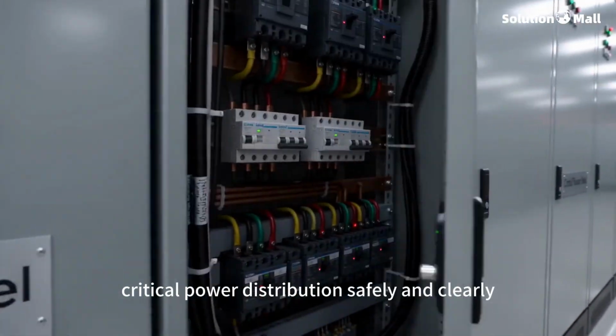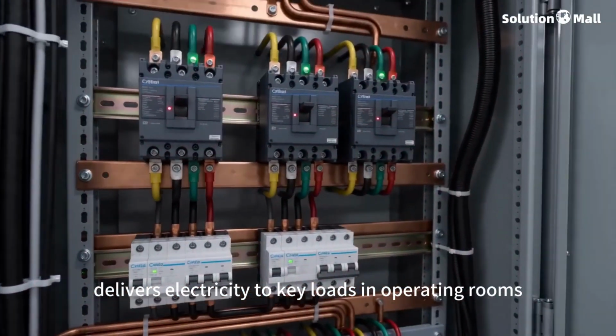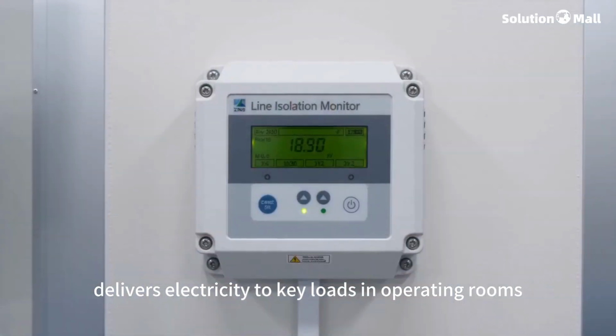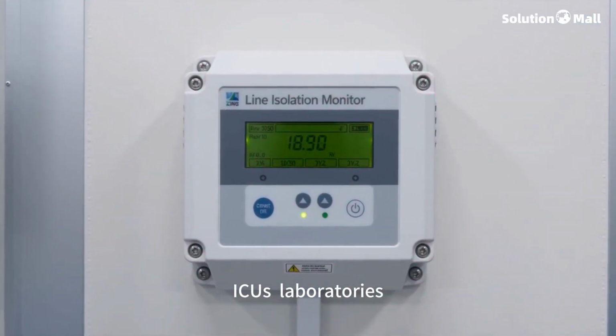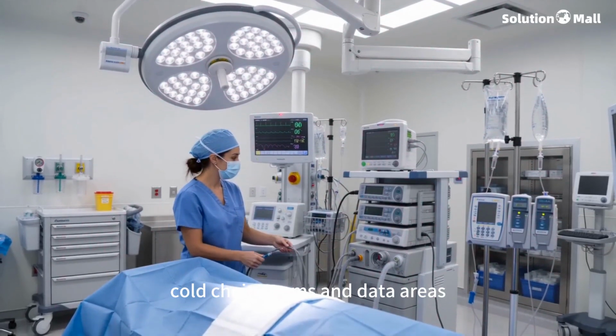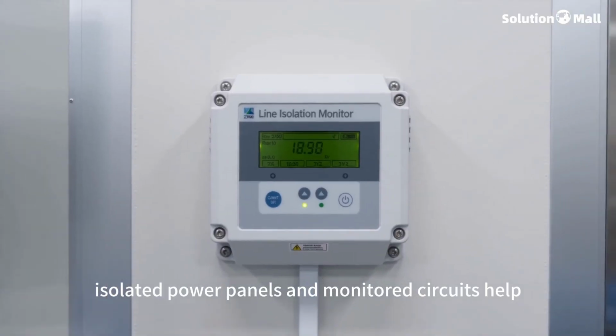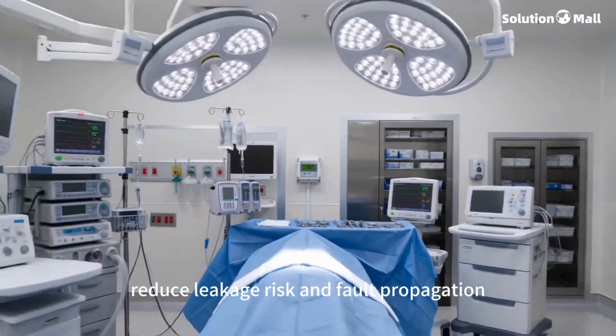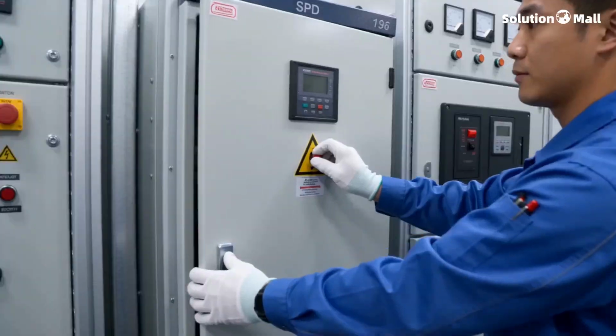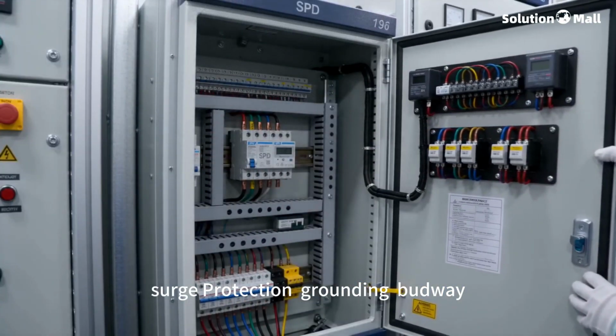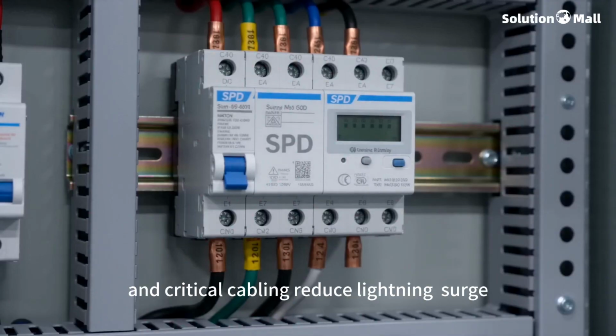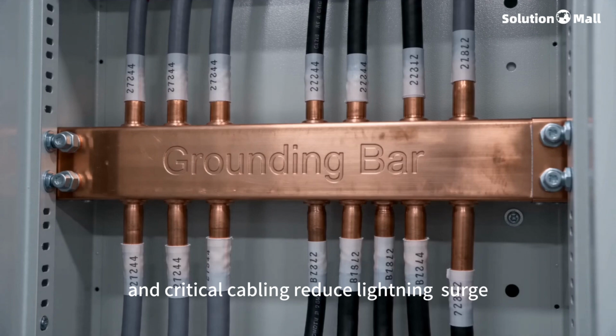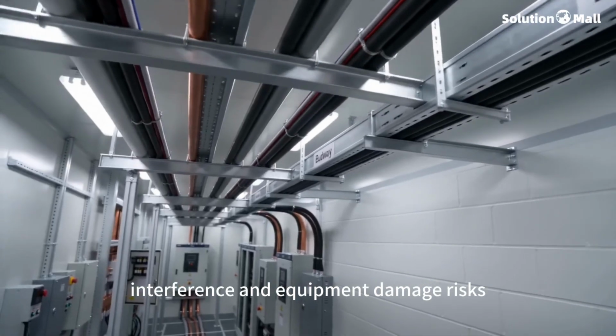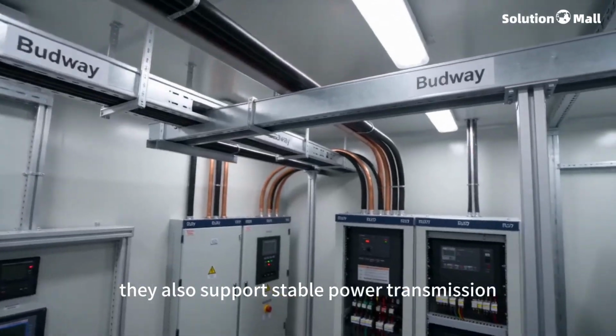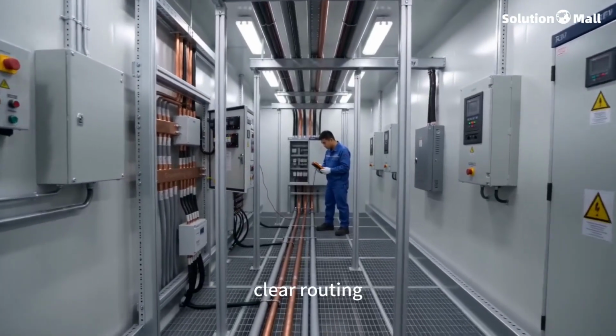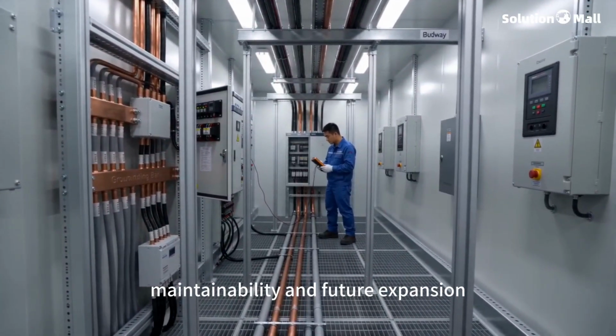Critical power distribution safely and clearly delivers electricity to key loads. In operating rooms, ICUs, laboratories, cold chain rooms, and data areas, isolated power panels and monitored circuits help reduce leakage risk and fault propagation. Surge protection, grounding, busway, and critical cabling reduce lightning, surge, interference, and equipment damage risks. They also support stable power transmission, clear routing, maintainability, and future expansion.